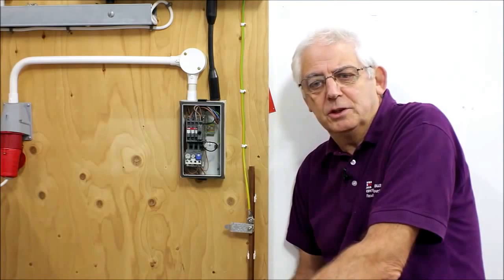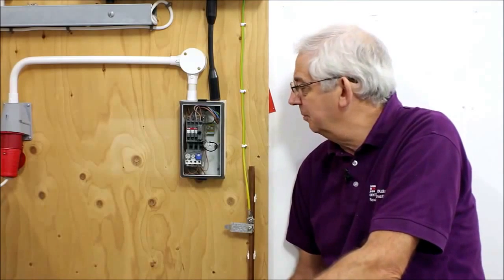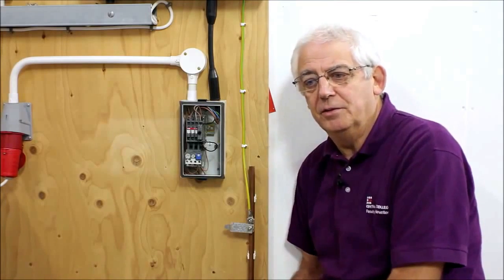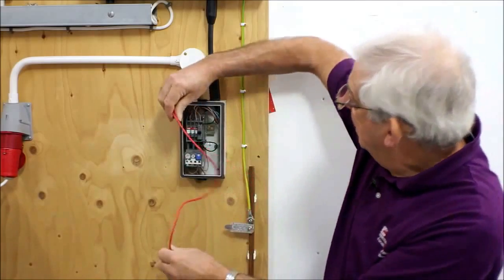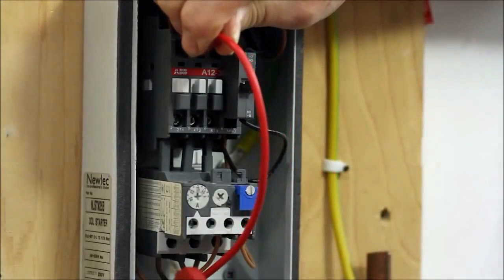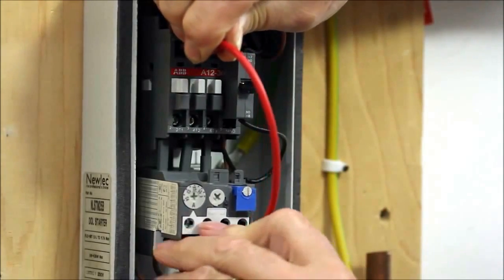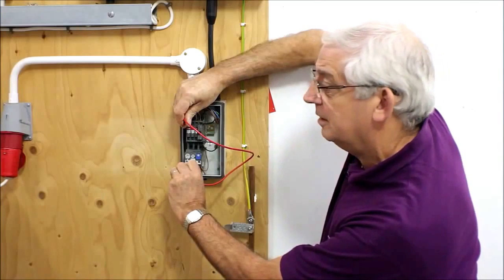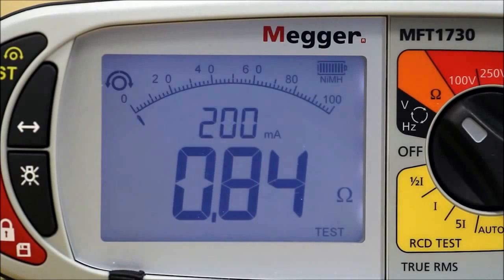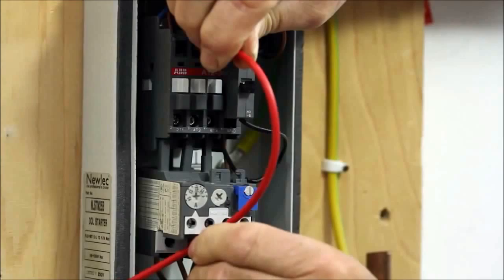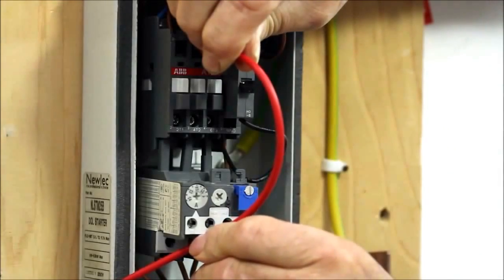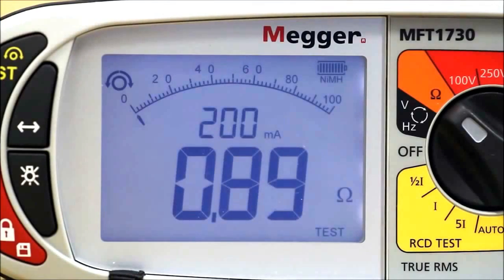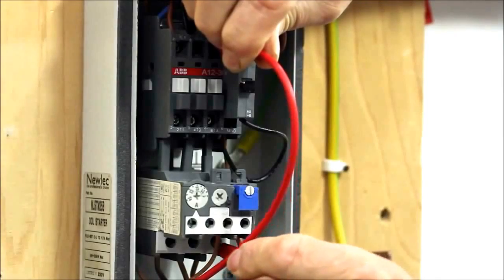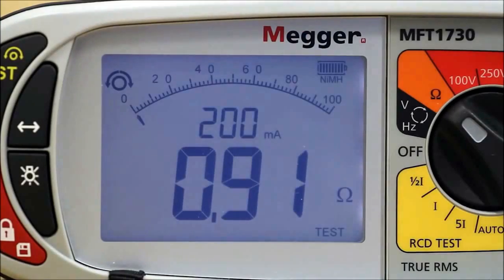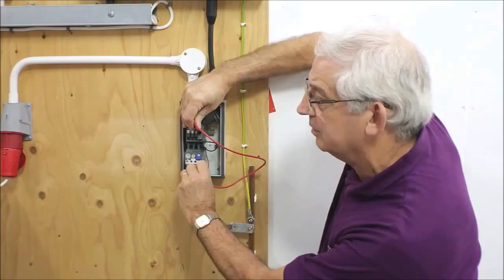If we try and measure across that, we're going to get a high reading, as I said before. So the easiest way to do it really is just to get a short lead and just short out between the incoming side of the starter and the outgoing side of the starter, and we'll get a reading. And we just need to do that on each line. So we've done L1, now L2, now L3. And the highest of those we would record as R1 and R2.